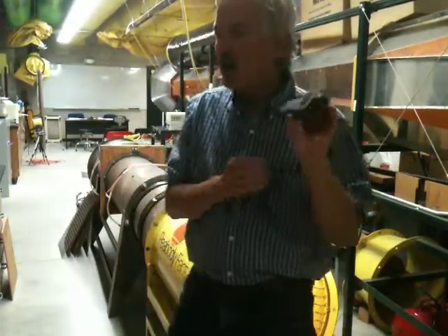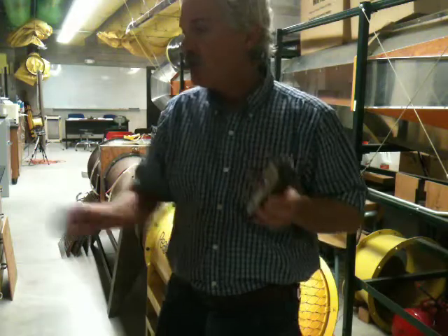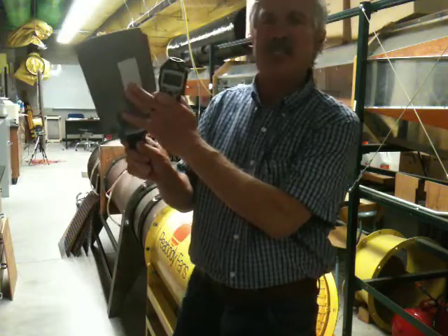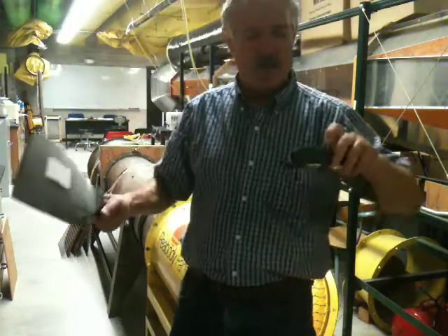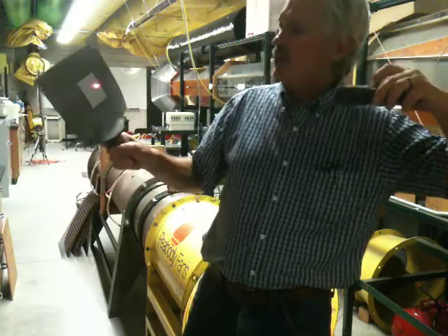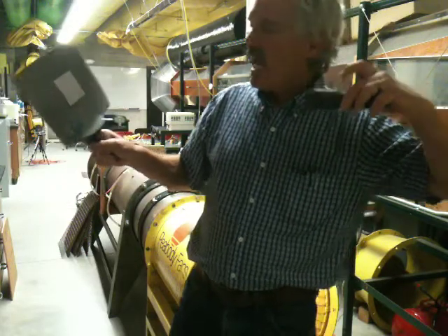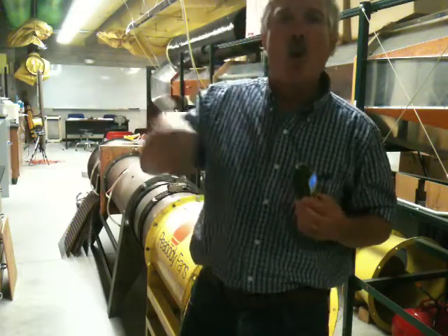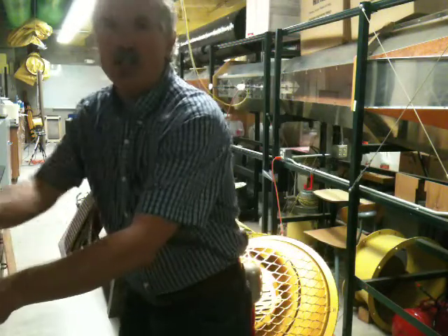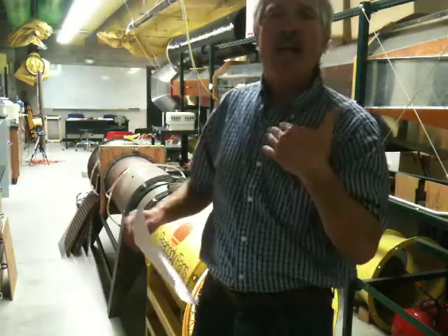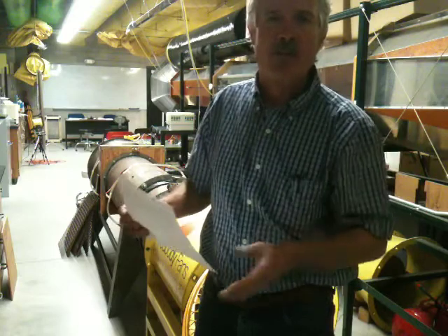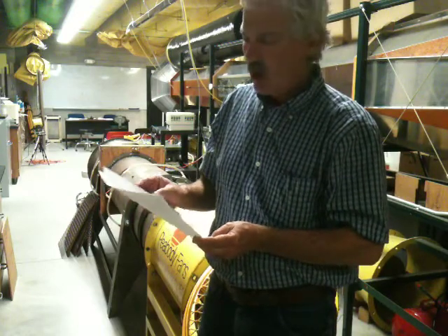So this is the laser tachometer. This is the only instrument in this lab session that you haven't used before, but it's fairly simple. To use it, you aim it at a reflective target, such as a piece of reflective tape on a fan blade, old broken fan blade here. You push a button and that illuminates a red dot, a laser, and you just aim this at a rotating target. You'd have one piece of tape for the whole rotor, and the way it works is that the laser light is reflected back when it encounters the reflective target. The instrument measures how long that takes in a very simple calculation to give you revolutions per minute, or RPM.